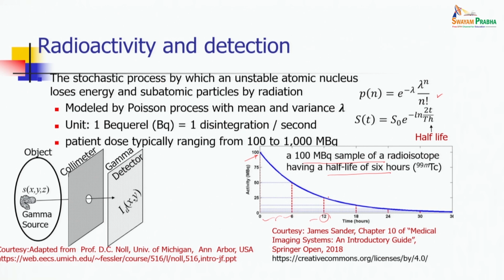For that we use a collimator, which controls the direction of detection. So, the detector knows that all this emission is coming along this line. Similarly, for every position there has to be some kind of collimation from where it is collecting radiation. There could be some interference, but we may ignore it, or we have to take care of that statistically when we do a better reconstruction.